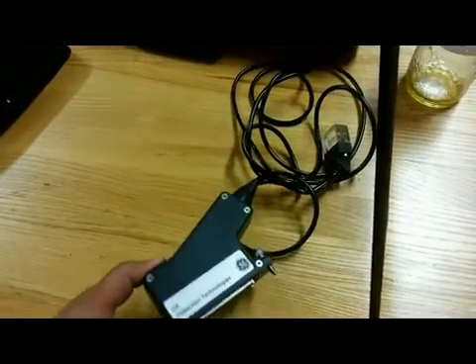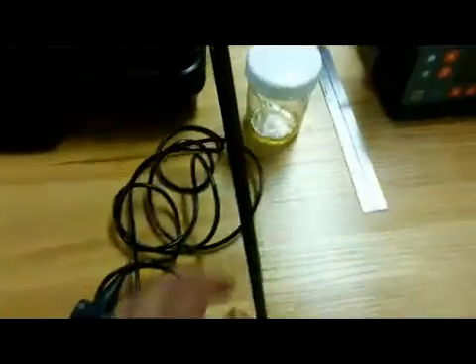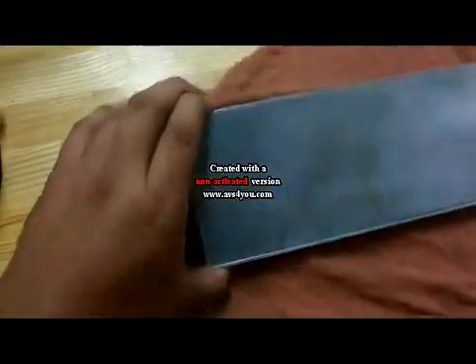The transducer is connected to a wedge. This wedge is the part which we pass over the sample. This is olive oil and a ruler, and this is our display screen. These are our samples — we have two types: the first one is a sample with visible holes, and the second one is a sample with hidden holes. Each sample is 9 inches by 4 inches. We have to check everything to be sure the device is fully functional.